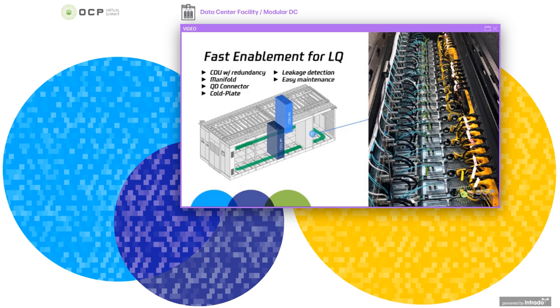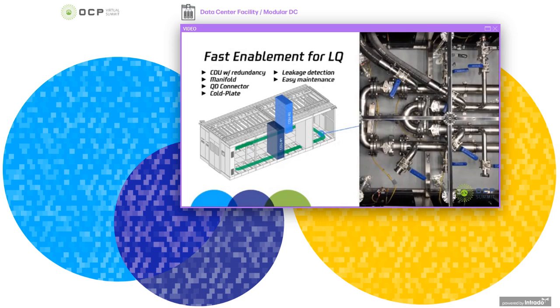The first picture is a rear view of the server, and you could find key components for liquid cooling: the manifold for liquid distribution inside the rack, and the quick disconnect between server and manifold for the supply and return. The second picture is about the secondary loop pipes, the liquid pipes for supply to the rack and return to the CDU. Different parts could be observed there. The dark soft pipe is the CDU to loop connection. The slim stainless steel pipe is the rack to loop connection. There are multiple valves and liquid detection cables on the rack. By the way, for this liquid implementation, at the server side we use cold plate technology.